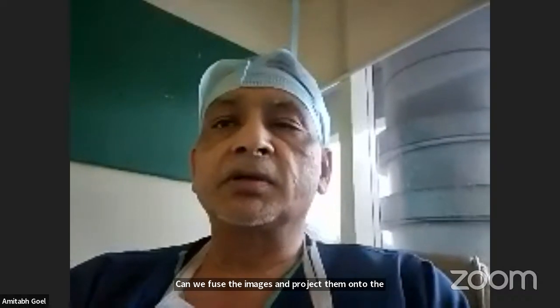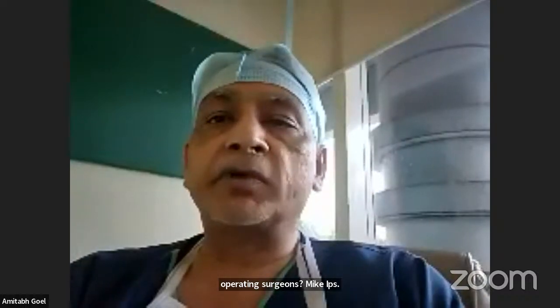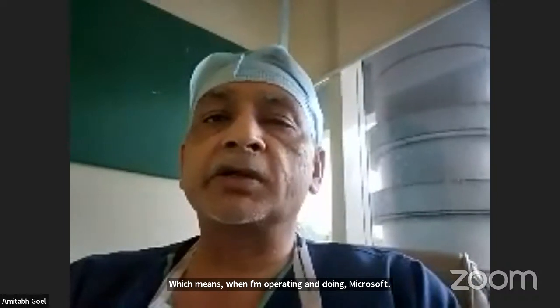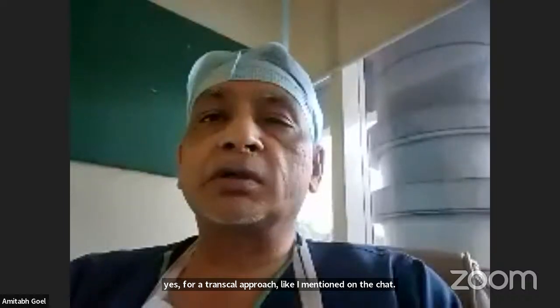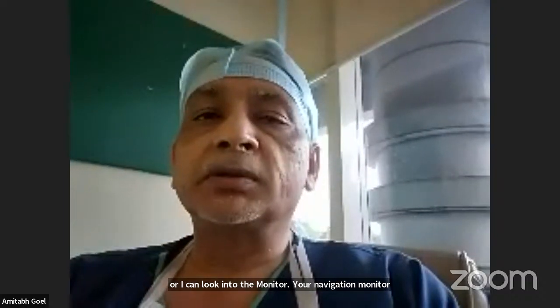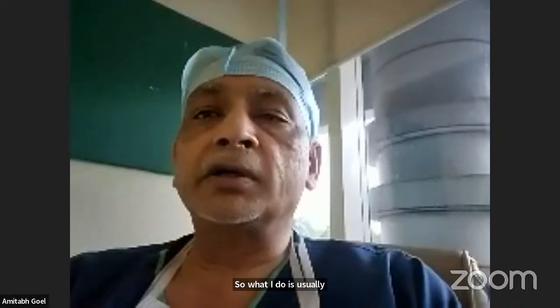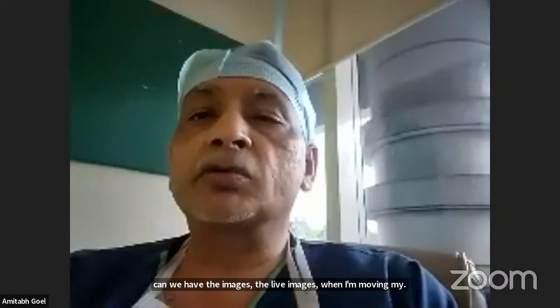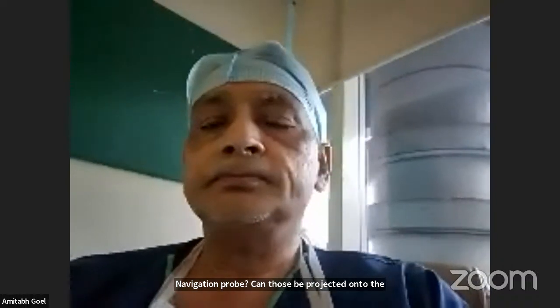Okay, so can we fuse the images and project them onto the operating surgeon's eyepiece? Which means when I'm operating and doing microsurgery for a transsulcal approach, like I mentioned on the chat, I'm lost because either I look into the microscope or I look into the monitor, your navigation monitor. I'm using your competitor's equipment. So usually I calibrate the suction tip, and then the first assistant looks at the monitor and I peep into the microscope. So can we have the live images, when I'm moving my navigation probe, projected dynamically onto the operating surgeon's eyepiece? Is that possible? Yes, sir, that's very much possible.